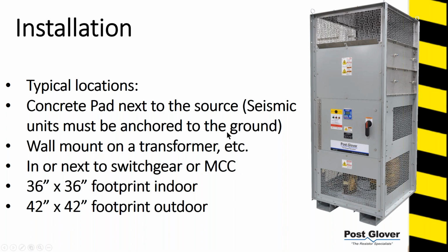But typical locations, you have a concrete pad. You can put it in an e-house. We have a lot of people put it in e-houses. You basically have these eye hooks you lift up into an e-house. Our footprint of 36 by 36 is pretty small for medium voltage high resistance ground. I know of at least 1 analog unit that is this big, but I don't know of any other digital units like that. Our outdoor is 42 by 42. I'm just giving you some examples of a footprint for what you would be looking at.